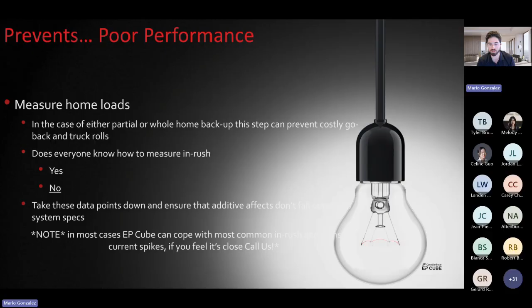Measure the inrush amps. That's why I recommend installing soft starters, because load equipment with high inrush amps, such as HVAC equipment and pool pumps, needs to be considered. If you don't take that into account when on backup without the grid to help, the system will short out and protect itself.